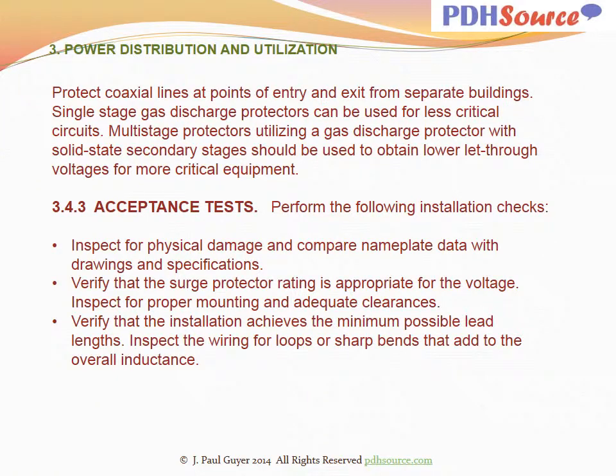Protect coaxial lines at points of entry and exit from separate buildings. Single stage gas discharge protectors can be used for less critical circuits. Multi-stage protectors utilizing a gas discharge protector with solid state secondary stages shall be used to obtain lower let-through voltages for more critical applications. With regard to acceptance tests, perform the following installation checks.